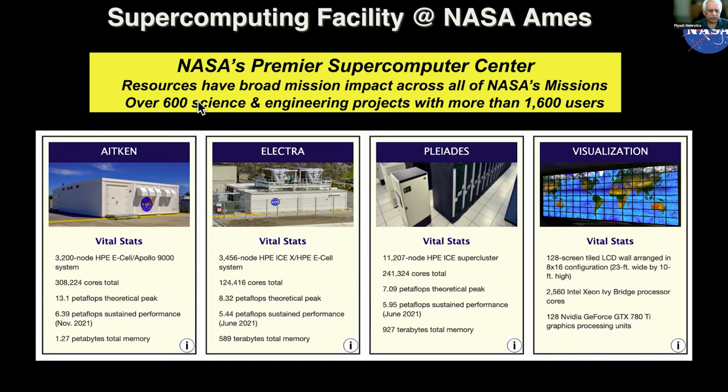When it becomes too hot, above 85 degrees, like it was yesterday, we have fiber curtains where water flows through, like in an evaporative cooler or a swamp cooler, which cools down the air, which then cools the systems. Aitken has a similar facility, but slightly different, with a closed water loop which cools the actual chips. When we did Electra, it became successful.